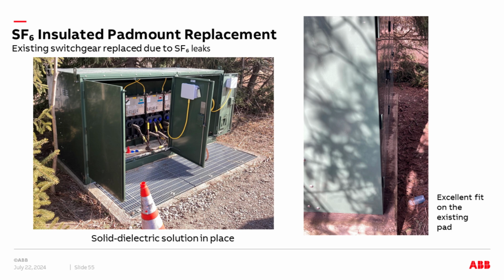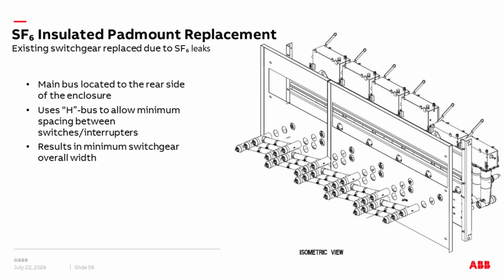So here's the new gear dropped into place. Again, it didn't require a different pad, it fit right on it, and the cables could be accommodated directly without having to cut and splice in sections. In this case, we used bus jumpers across the back of the gear in order to keep the thing as low in height as possible, but still interconnect all the ways.